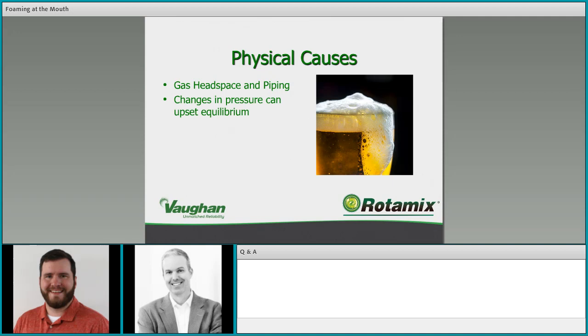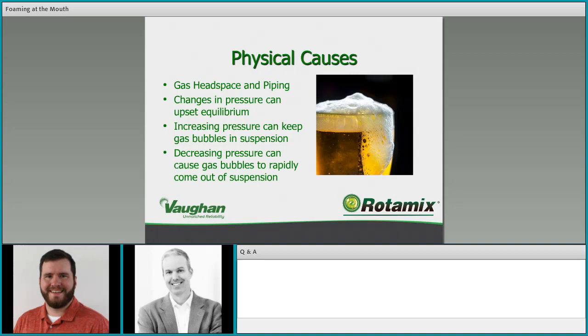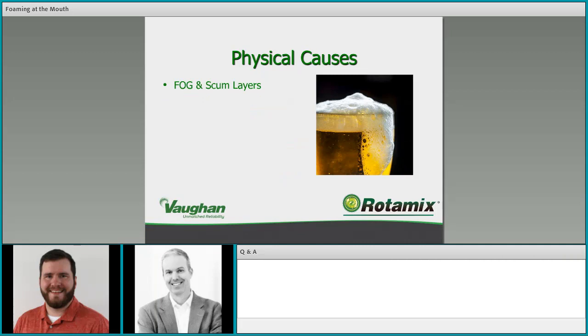Other physical causes: gas headspace and piping — changes in pressure can upset equilibrium of the solid, liquid, and gas phases. Increasing pressure in your headspace can keep gas bubbles in suspension and dissolve more CO2 into the digester sludge. If you decrease that pressure, you can cause those gas bubbles to rapidly come out of suspension, and if you have the right scenario for foaming, all those bubbles coming out can definitely cause a foaming event.